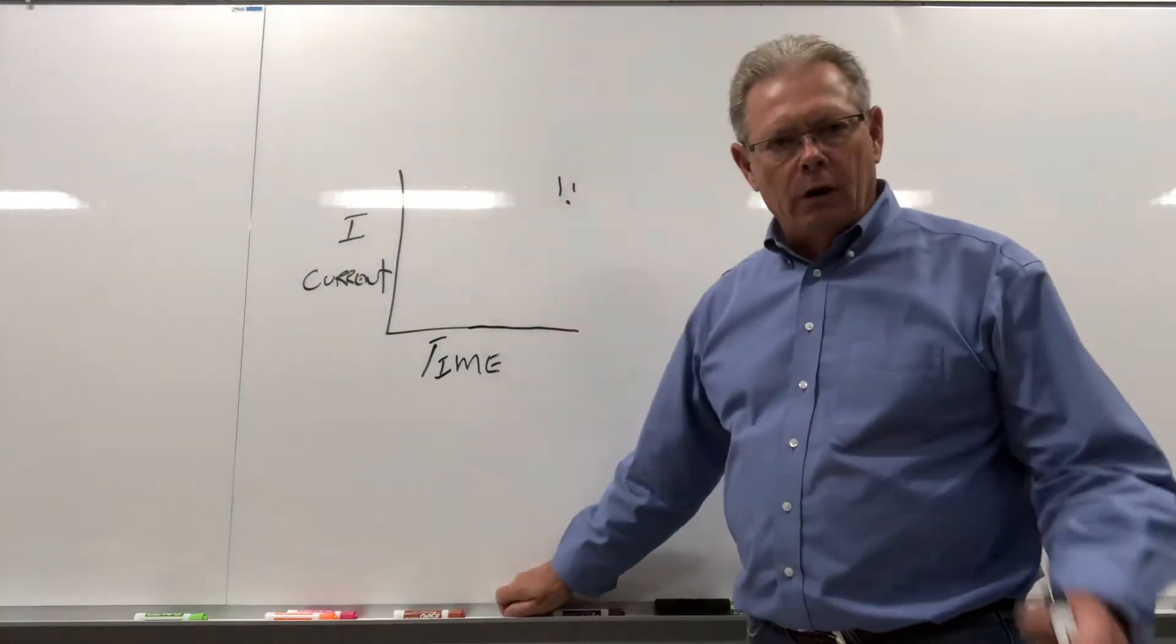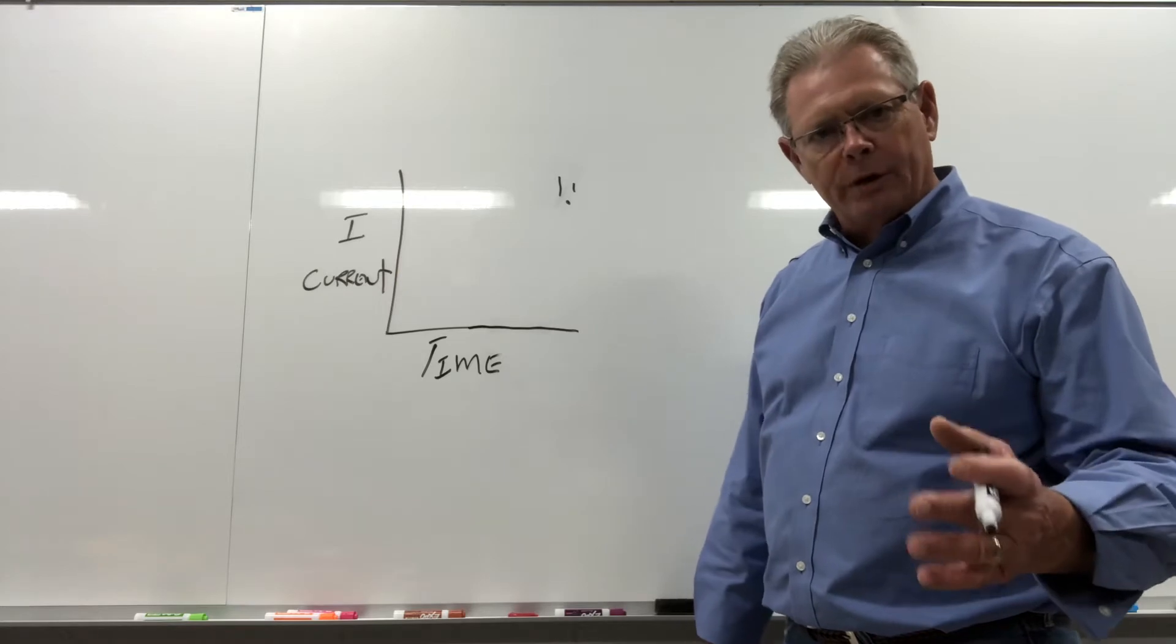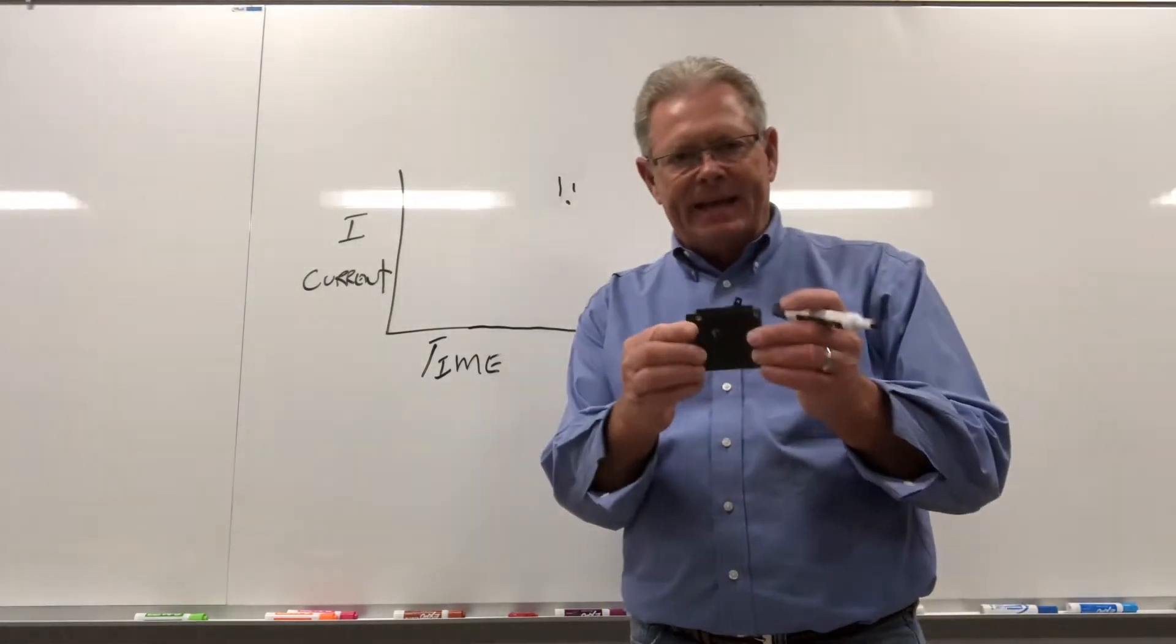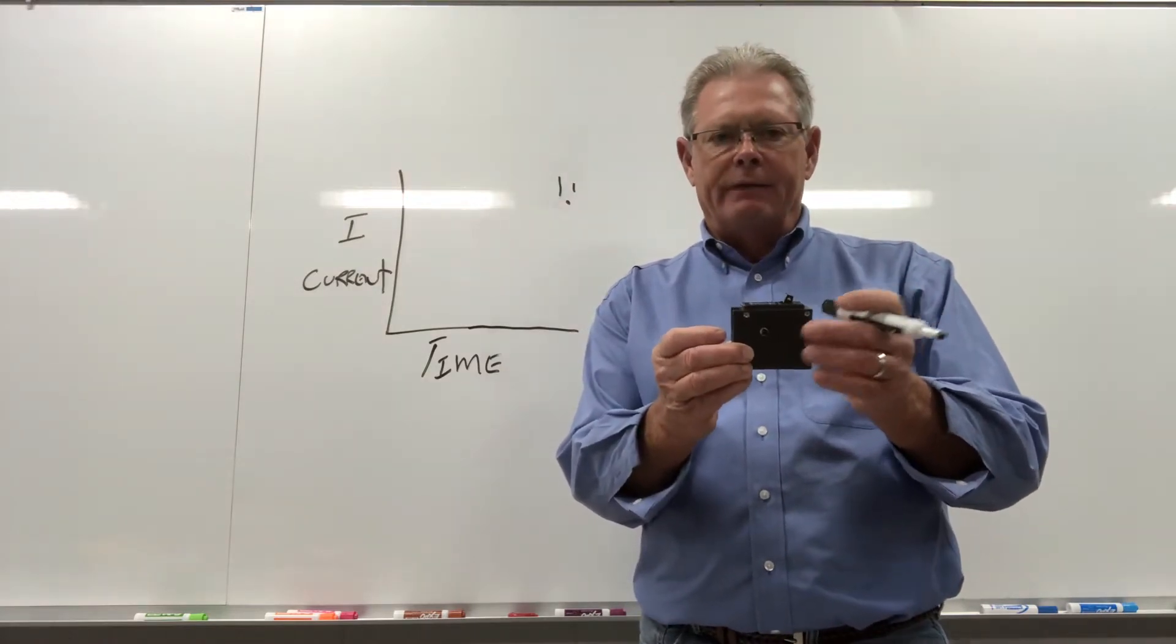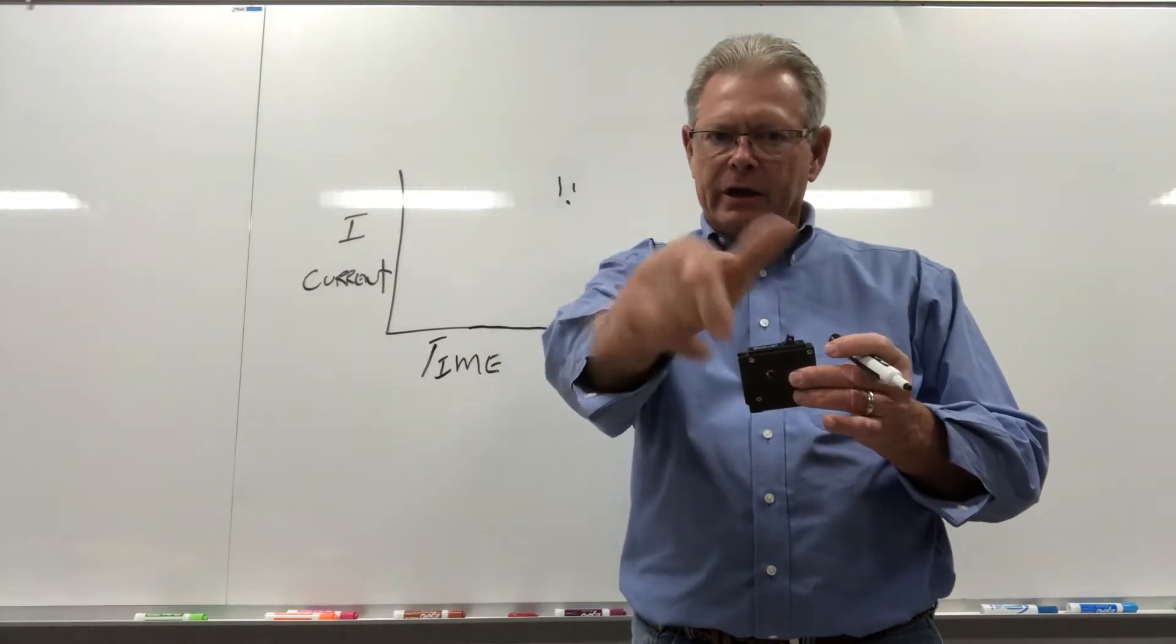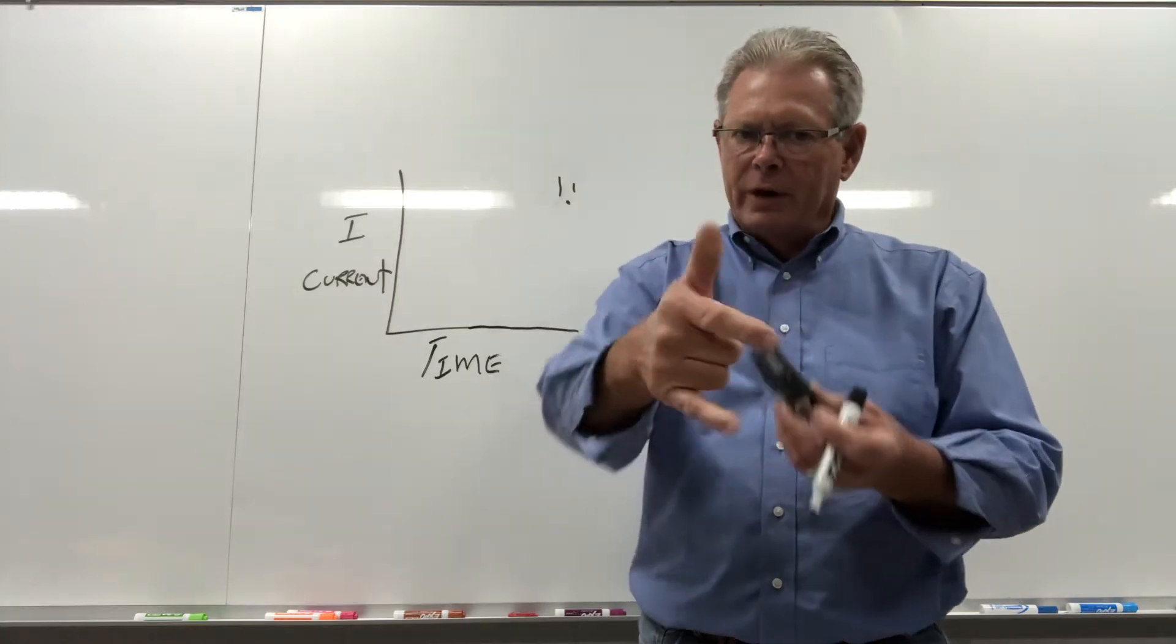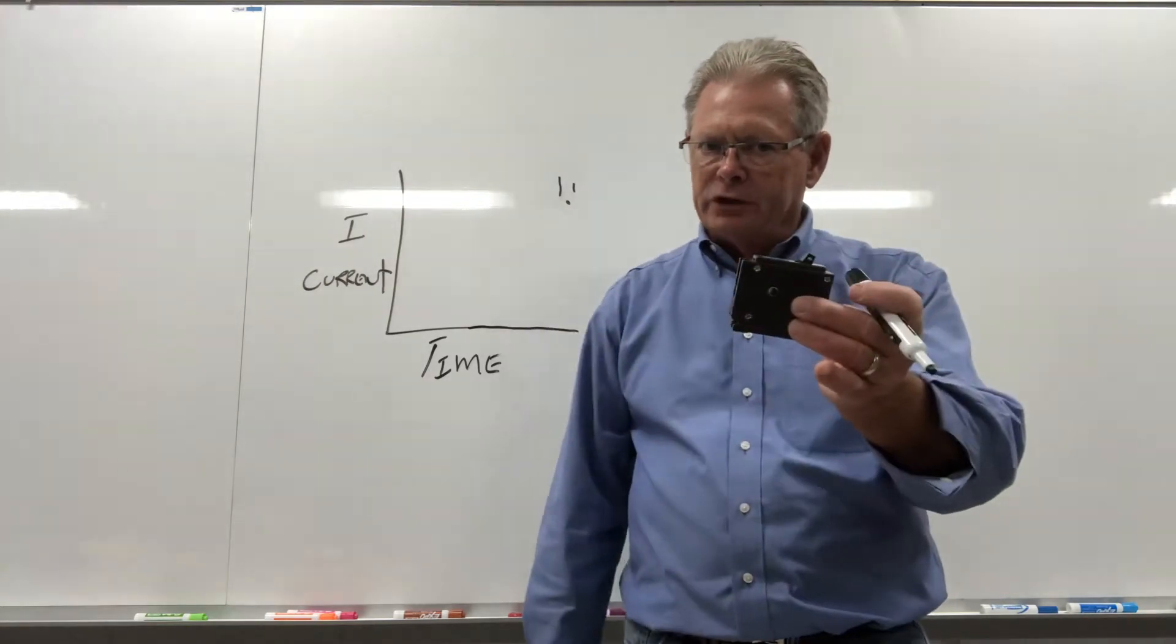Okay, we're going to talk about different conditions that will trip a circuit breaker. This is an inverse time circuit breaker. Inverse time means it works off heat. It works like a seesaw. The higher the current, the quicker it trips. The lower the current is over the rating, the longer it takes to trip.